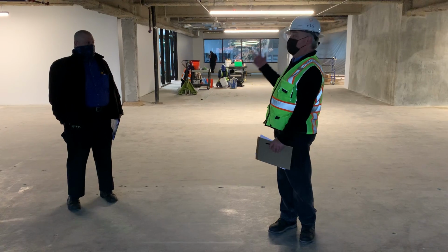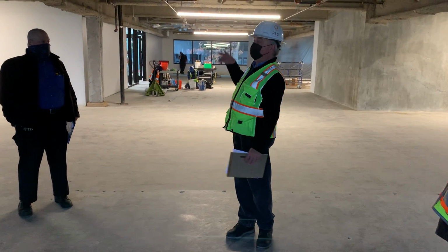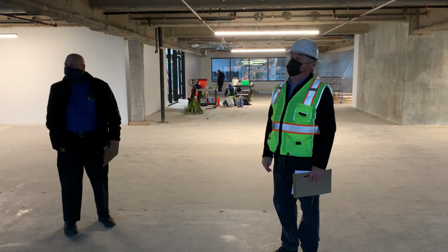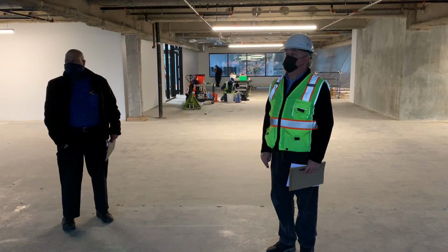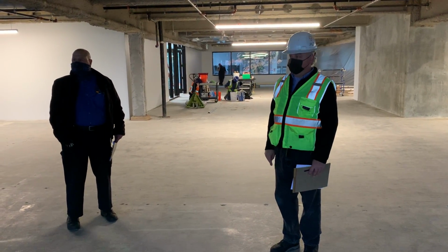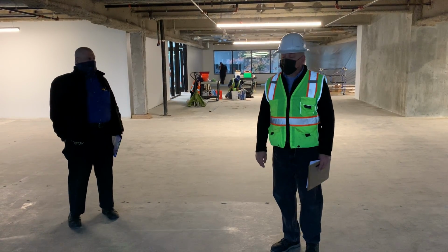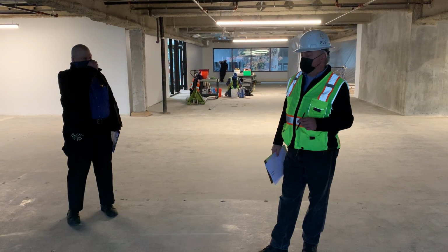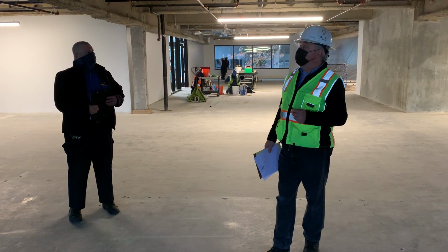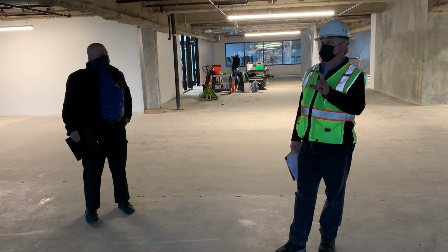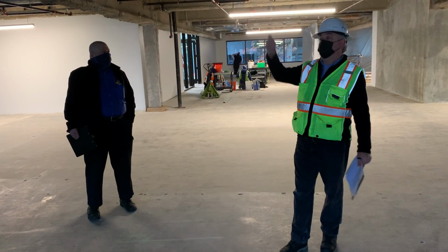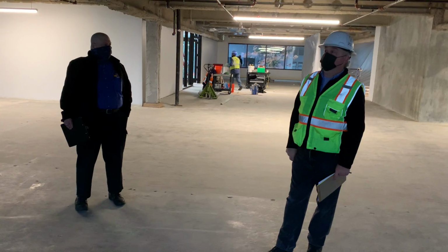And again, that's true on all 8 restrooms, 2 on each end of the floor, on both floors. And that timer's controlled where? At the switch in the door, inside the room? In the sensor itself. In the sensor on the ceiling? Yes. There isn't one included in the bill of materials for this project, but there is actually a little handheld tool, a little infrared transmitter, that can be used to adjust sensor sensitivity and timeout.